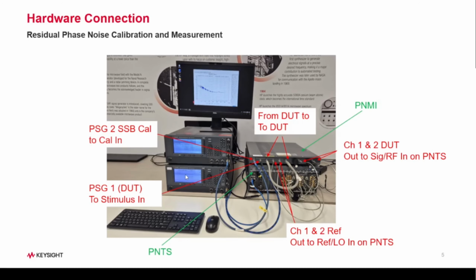So the PSG on the bottom here is my PSG1 or my device under test. PSG2 will then provide the cal-in signal. So that's to the first port, and the stimulus is to the second port. I have a cable connected from that to that. This and the two ports in between are the LO in ports to the phase noise test system. So you would want to connect this first ideally, as they are sitting below the RF ports on the phase noise test system. That would just make it a little easier when you're connecting them in.